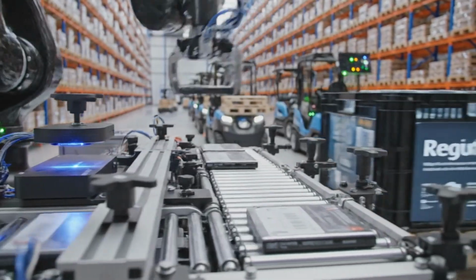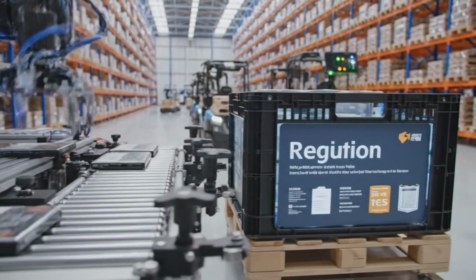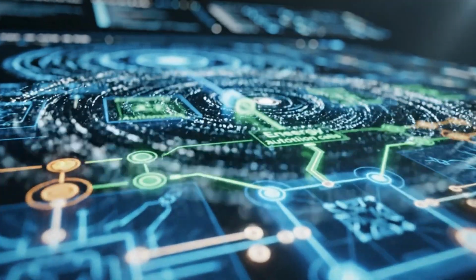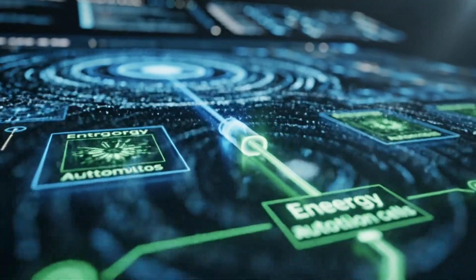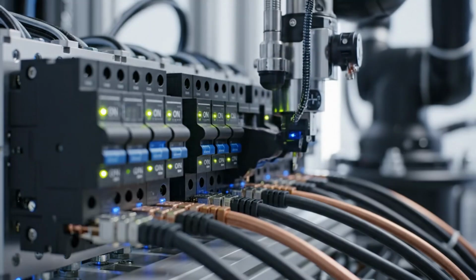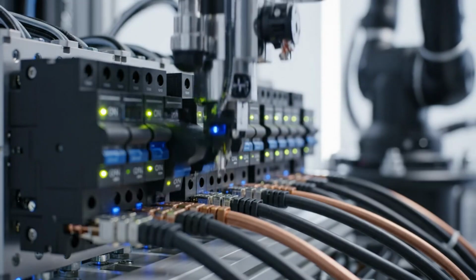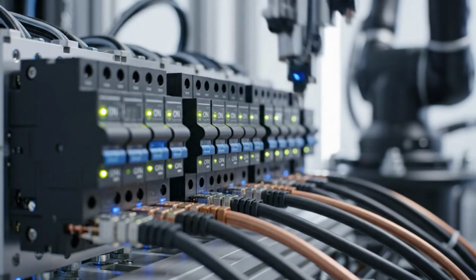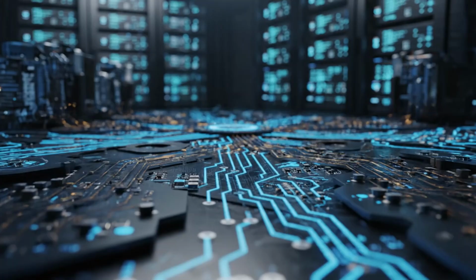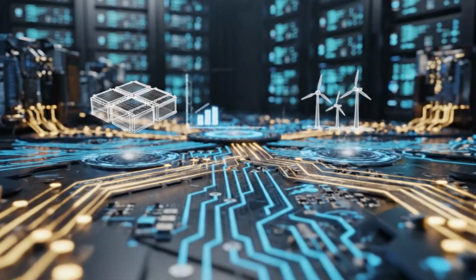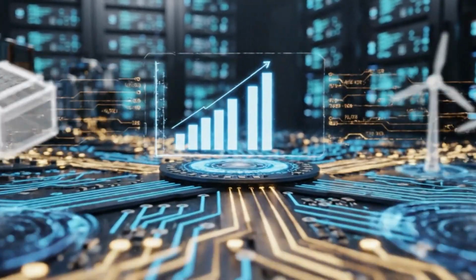Electrical performance testing follows. Power systems are energized under controlled conditions while current flow, voltage stability, and switching behavior are monitored in real time. Protective devices are tested to ensure they respond correctly to overloads, short circuits, and fault conditions. These tests confirm that systems act decisively when abnormal conditions occur, not milliseconds too early and never too late.